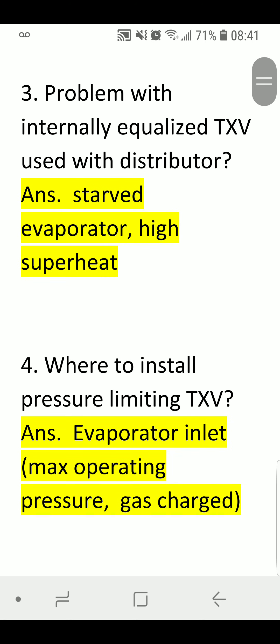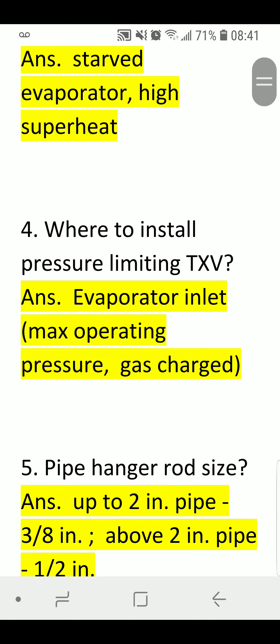Problem with Internally Equalized TXV used with Distributor. Answer: Starved evaporator, high superheat.